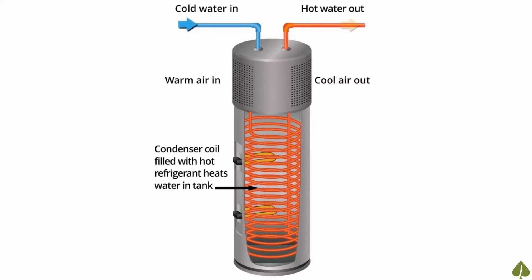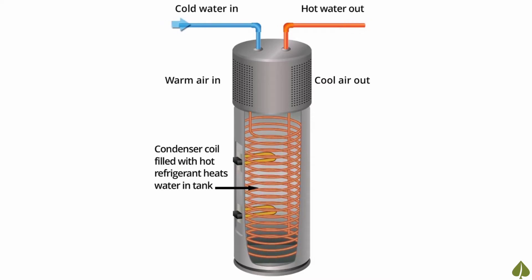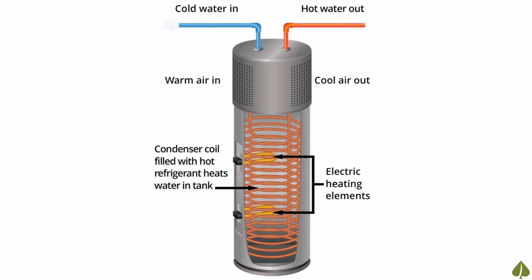When a demand for hot water occurs, like washing hands in a sink, the heat pump water heater relies solely on the heat pump to maintain the water temperature in the tank, thus saving energy by not using electric resistance heating. When a higher demand for hot water occurs, like a long shower, some heat pump water heaters temporarily switch to use electric resistance heating to heat the cold water entering the storage tank, and then switch back to using the heat pump to maintain the water temperature set point.